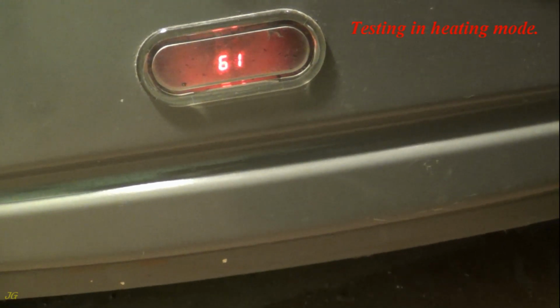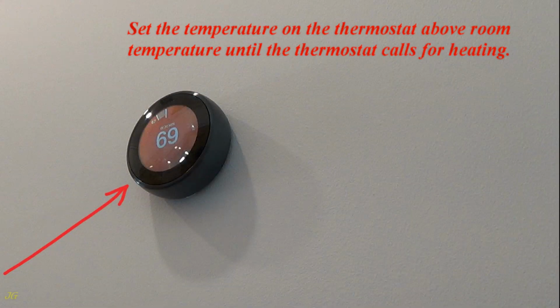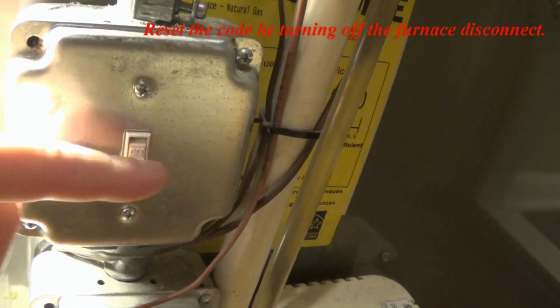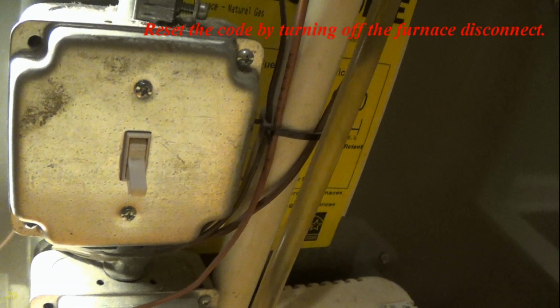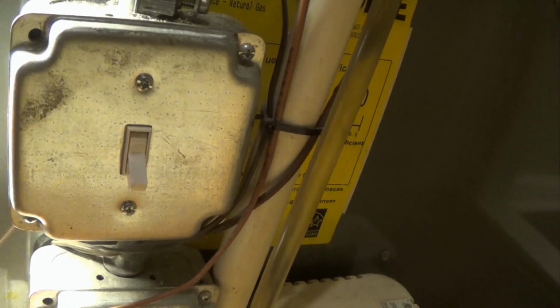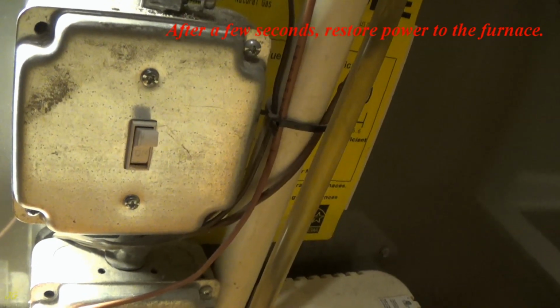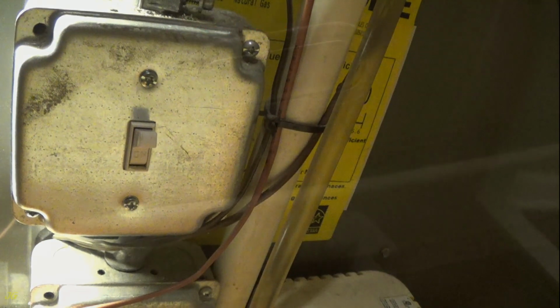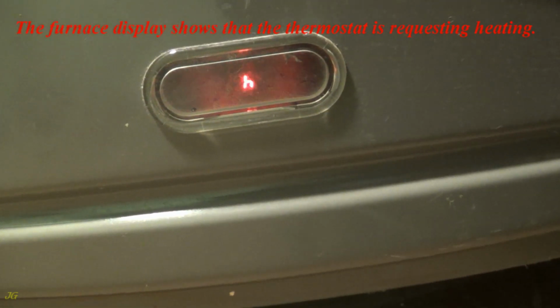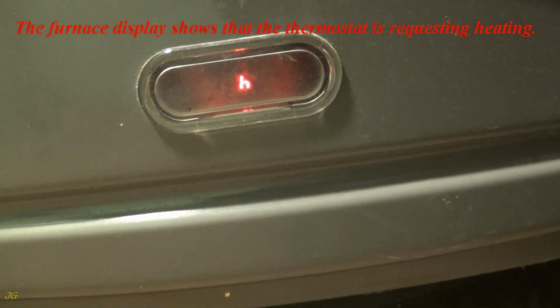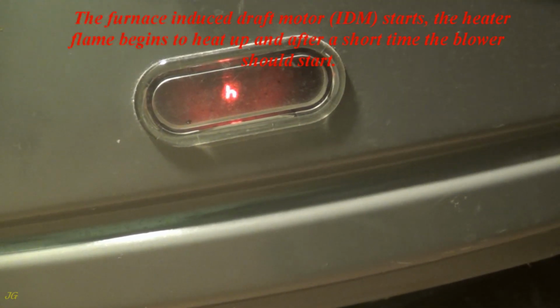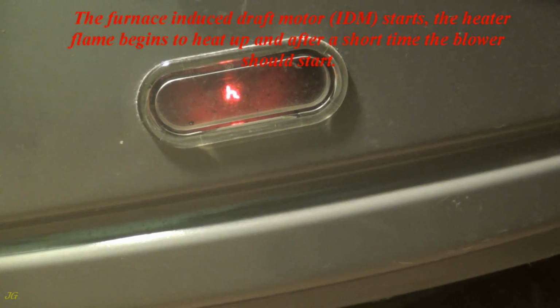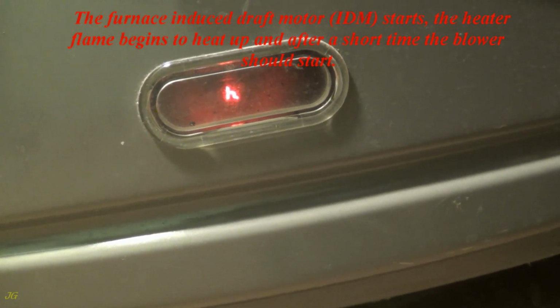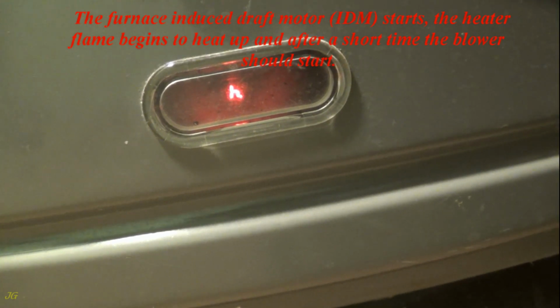Testing in heating mode. Set the temperature on the thermostat above room temperature until the thermostat calls for heating. Reset the code by turning off the furnace disconnect. After a few seconds, restore power to the furnace. The furnace display shows that the thermostat is requesting heating. The furnace-induced draft motor, IDM, starts. The heater flame begins to heat up and after a short time the blower should start.